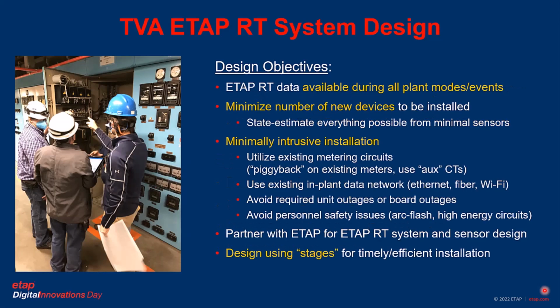These are our design objectives. First of all, the ETAP RT data should be available during all plant modes and plant events. Also, we want to minimize the number of new devices to be installed. That's very important. We talked about that earlier. In other words, let's estimate everything we possibly can from as little as we can possibly install. We want to have minimally intrusive installation.